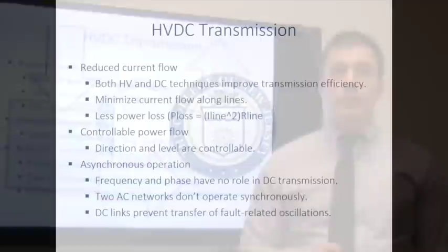Now, this type of link is advantageous for several reasons, one main one being reduced current flow. Both high voltage and direct current techniques individually, either high voltage or DC, improve transmission efficiency by minimizing current flow along lines. This is important because real power loss is proportional to line current squared, as defined by good old P equals I squared R. Another advantage of HVDC is controllable power flow.